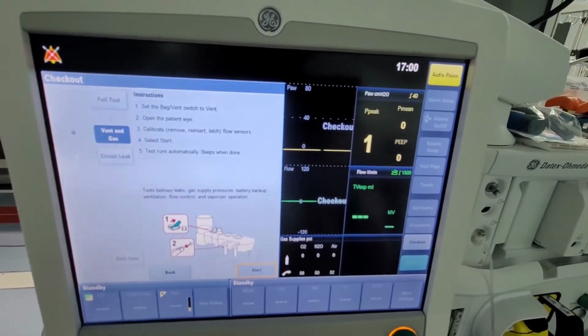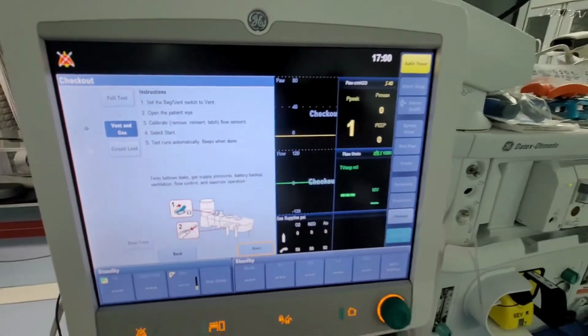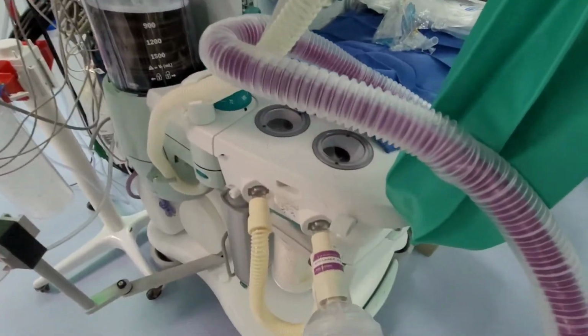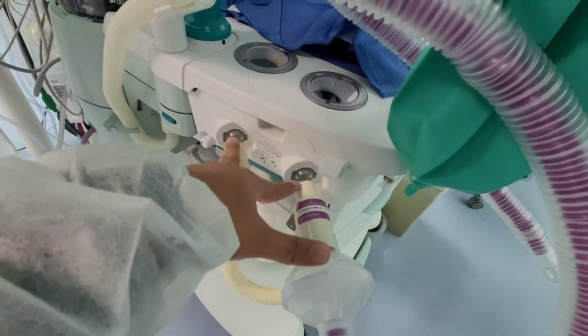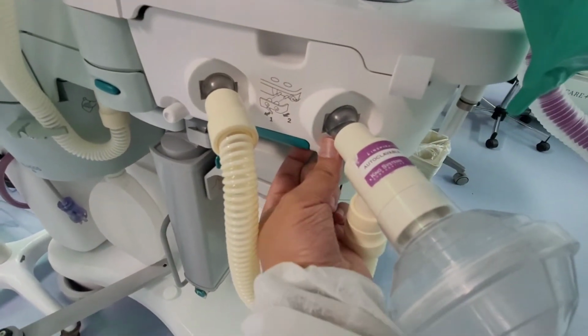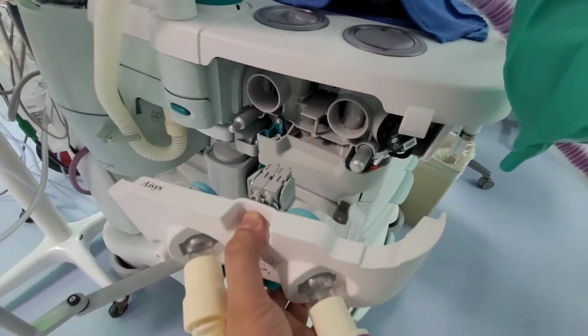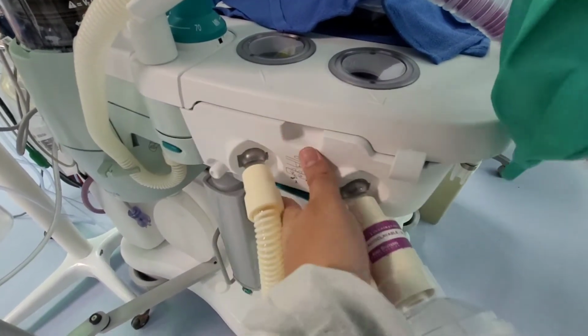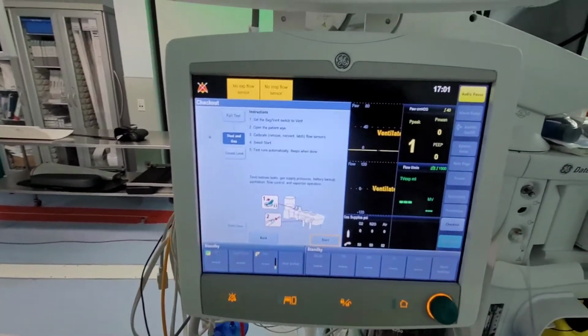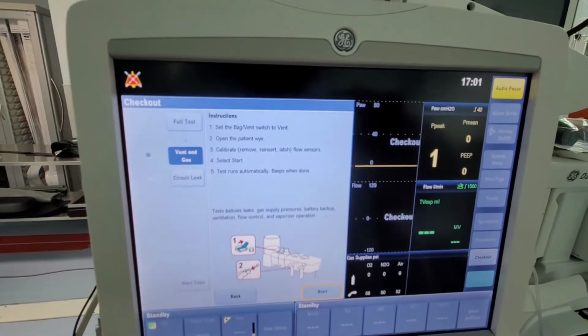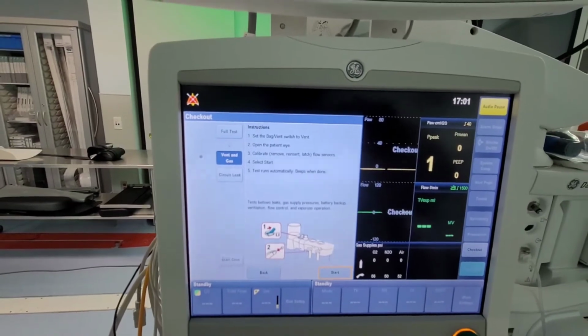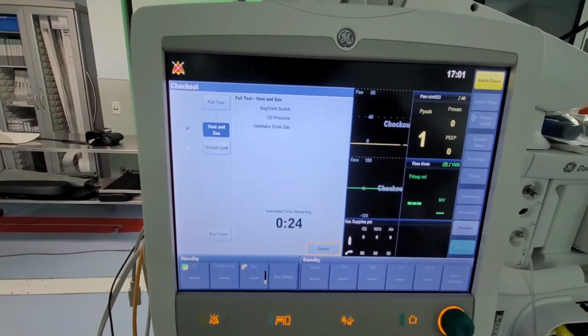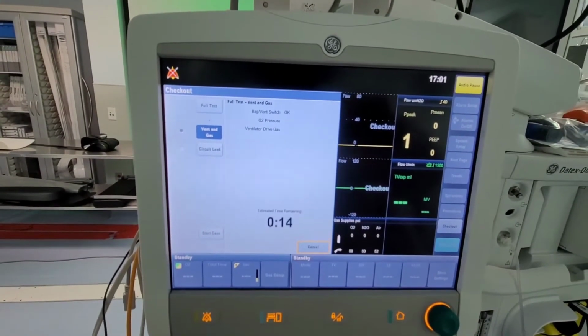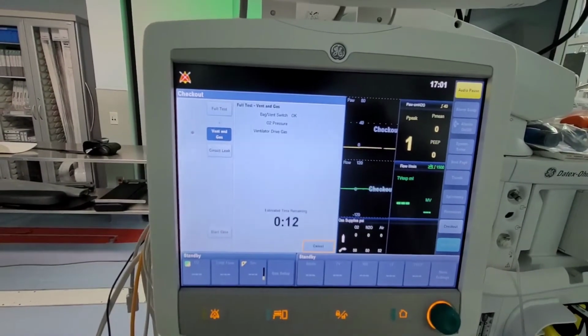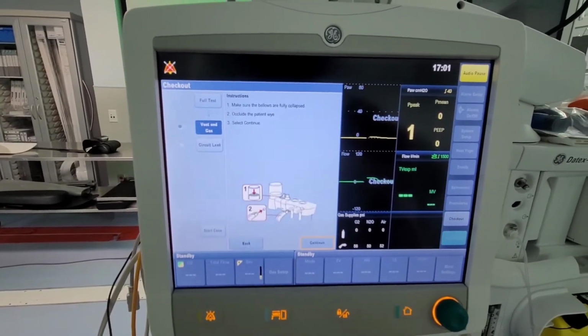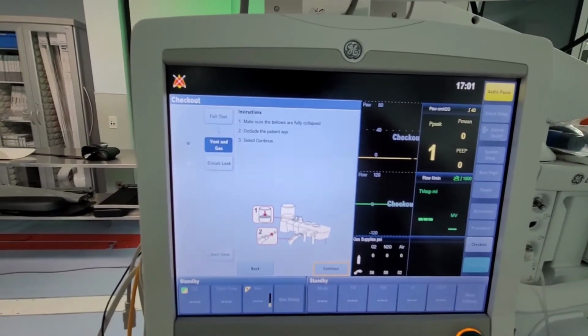The third step says calibrate, or remove and reinsert, the flow sensors. This is optional, it's not needed, but if you want to, you can. Where the flow sensors are, you'll have a green switch. You pull on that switch, pull on the whole module, and reset it. You'll see here that there are no inspiratory or expiratory flow sensors. It'll go away once it picks them up. Now we can press start. It's going to check the switches, O2 pressure, and the ventilator drive gas. Once that's completed, it'll move on to the next set of instructions.